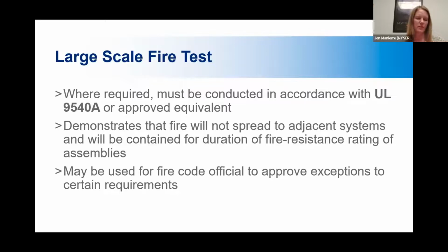And so for one example, I mentioned minimum separation requirements earlier. If there's a section of the code that says you must space different blocks of batteries in each system at least 5 feet apart, if this large scale fire test shows that you can light one of them on fire within 3 feet of another one, and it's not going to spread, the fire code official can use that information to say, okay, well, you can put them less than 5 feet together. You can put them 3 feet together because this large scale fire test that was conducted in a laboratory shows it to be safe.